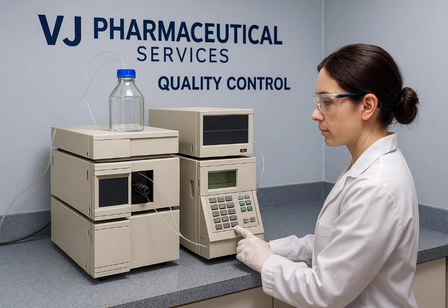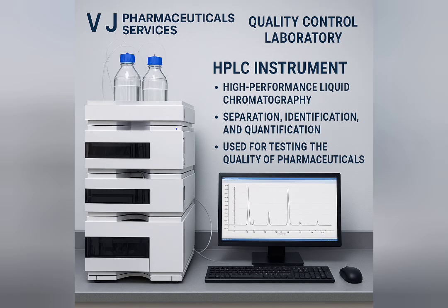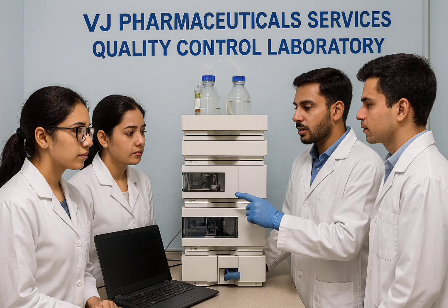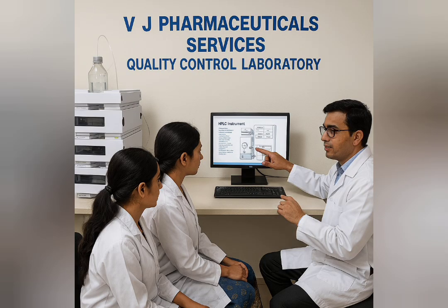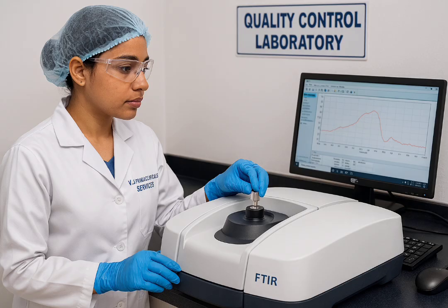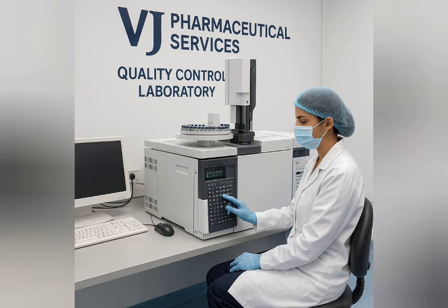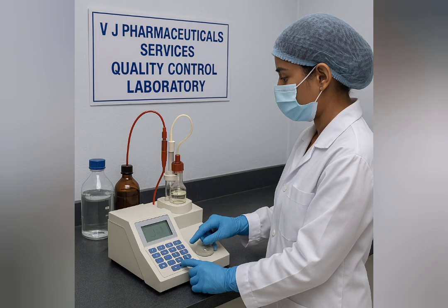Interpretation. For a reversed phase LC column where A is water and B is organic, this first run shows sample constituents that are all polar. So, the separation is poor because the substances experience little partitioning on the stationary phase. In other words, the weak starting solvent condition brings the sample constituents off too early. To cause the substances to partition more into the stationary phase, we reduce the slope of the gradient so that the mobile phase strength does not increase as quickly. The substances retain longer and begin to separate from one another. Notice that we still flush the column with strong solvent at the end of the run to effectively clean the column. We reduce the gradient slope again until we begin seeing a good separation within the time frame.